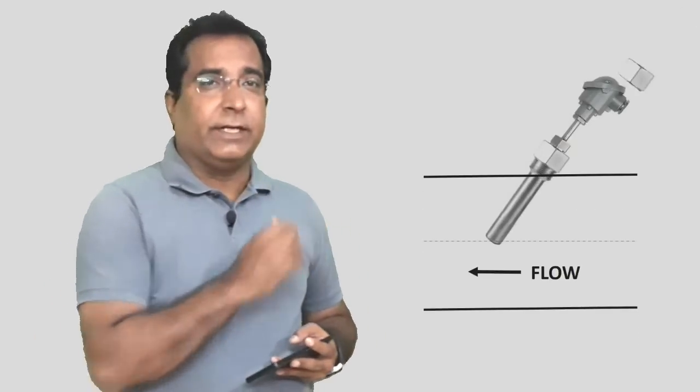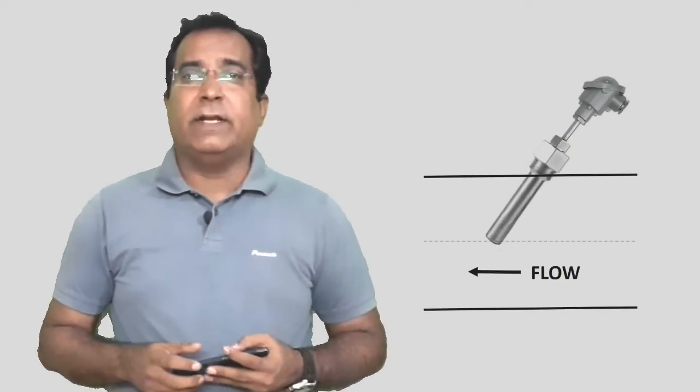Many times the sensor thermosheath is worn out due to flow of slurry, abrasive material, or dusting gas due to abrasion. For this reason, the well or sensor may be inserted inclined in the direction of flow. The way you see on the screen. In this way, sensor life can be increased.